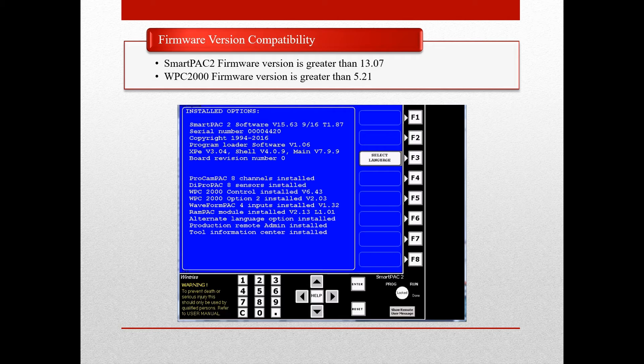With new boards, the SmartPAC2 firmware version needs to be higher than 13.07, and the WPC-2000 firmware version needs to be higher than 5.21.